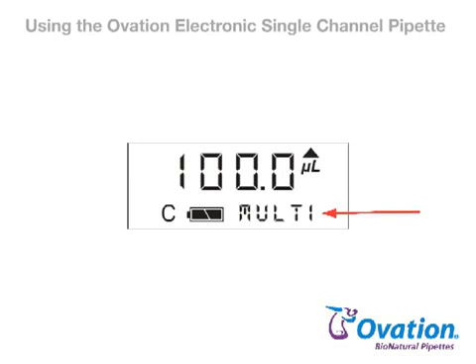The right corner of the LCD indicates the liquid handling function, setting, or prompt that is active. The symbol indicates the next portion of the aspirate or dispense cycle to be performed. The volume and values during setup are shown on this area of the LCD. The character C is displayed on the LCD when the cal factor has been changed from the factory setting of 1.000, and the battery icon indicates the remaining battery capacity.